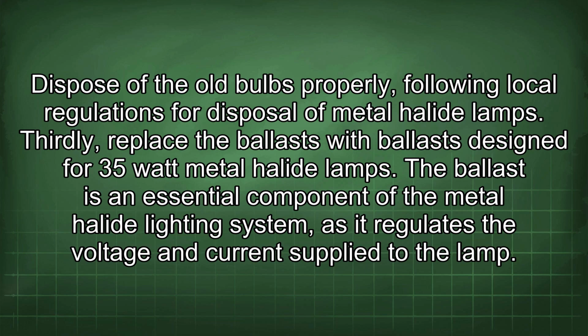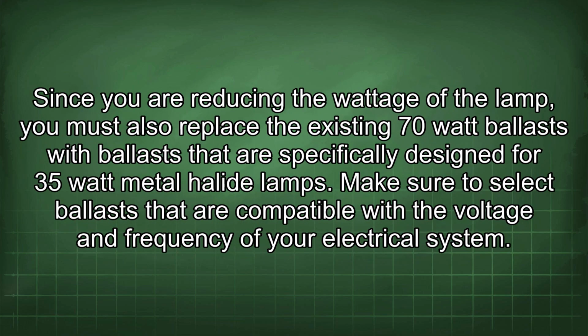Thirdly, replace the ballasts with ballasts designed for 35-watt metal halide lamps. The ballast is an essential component of the metal halide lighting system, as it regulates the voltage and current supplied to the lamp. Since you are reducing the wattage of the lamp, you must also replace the existing 70-watt ballasts with ballasts that are specifically designed for 35-watt metal halide lamps. Make sure to select ballasts that are compatible with the voltage and frequency of your electrical system.